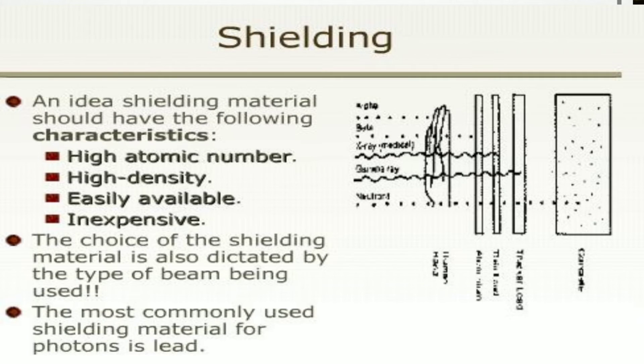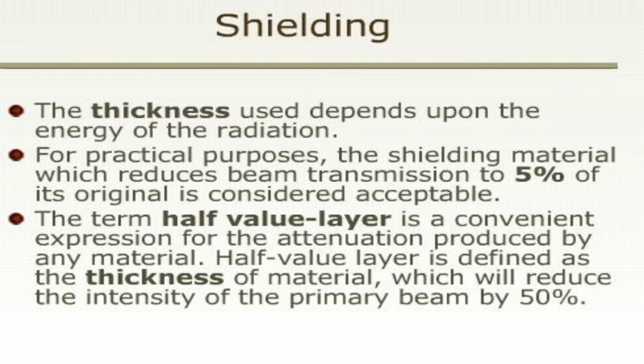The shielding material should have characteristics like high atomic number, high density, easily available, and inexpensive. The choice of shielding material is dictated by the type of beam used, and the most commonly used shielding material for photons is lead. Thickness depends upon the beam energy. For practical purposes, shielding material which reduces beam transmission to 5% of its original is considered acceptable.